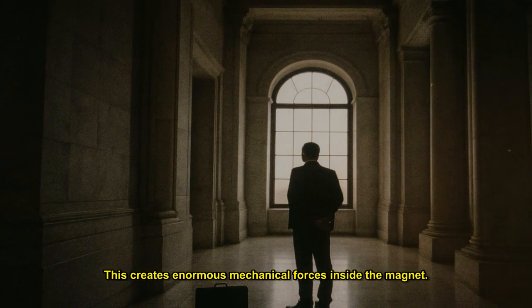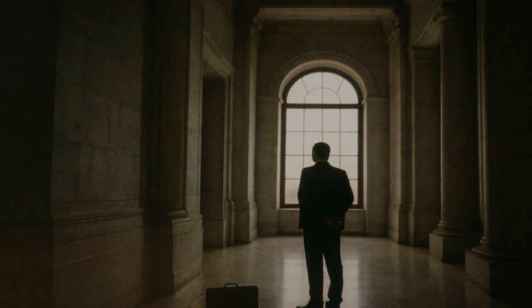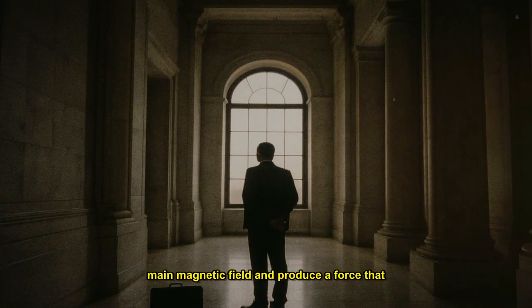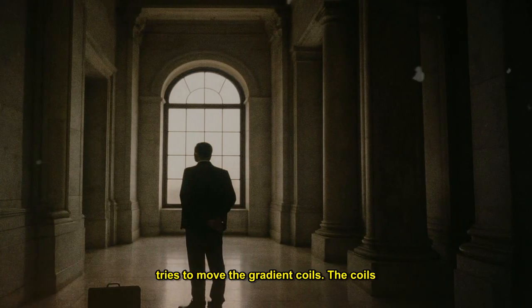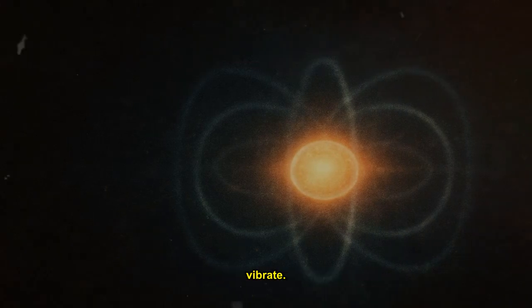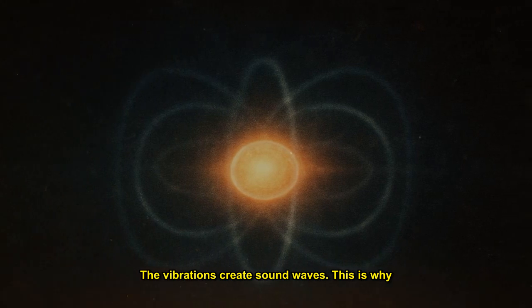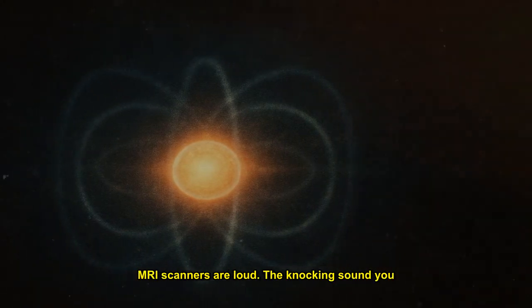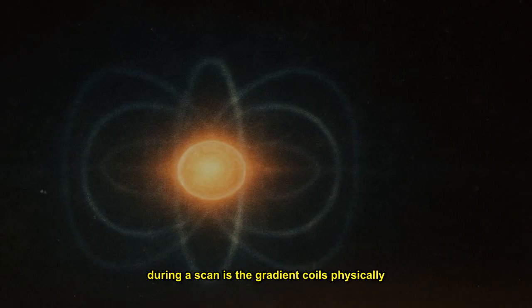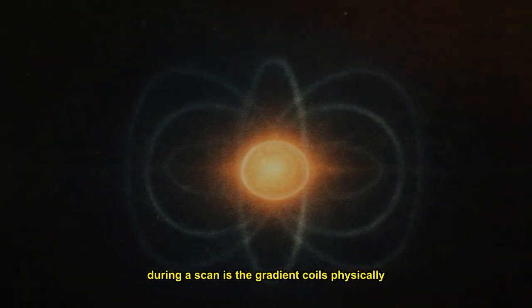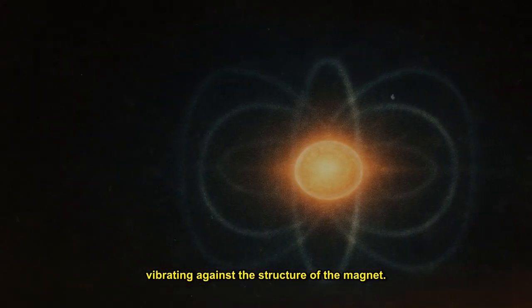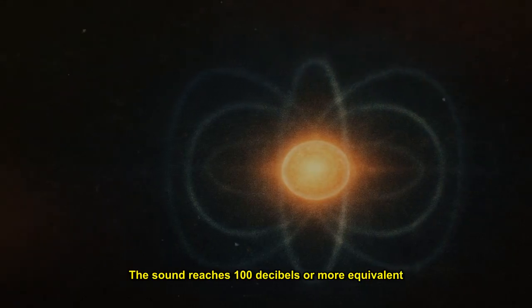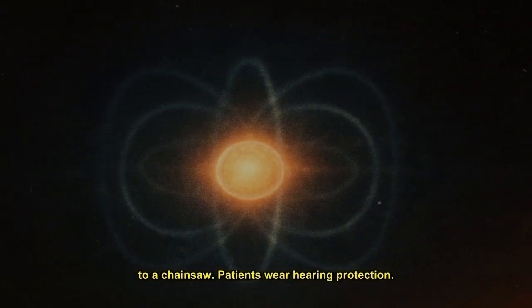This creates enormous mechanical forces inside the magnet. The gradients interact with the main magnetic field and produce a force that tries to move the gradient coils. The coils vibrate. The vibrations create sound waves. This is why MRI scanners are loud. The knocking sound you hear during a scan is the gradient coils physically vibrating against the structure of the magnet. The sound reaches 100 decibels or more, equivalent to a chainsaw.